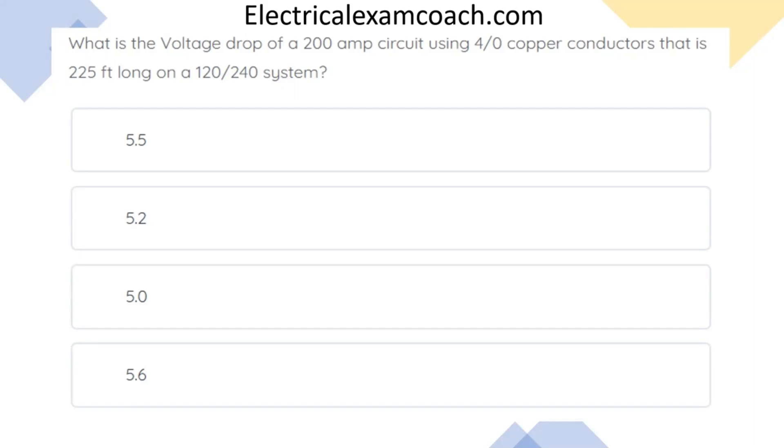What is the voltage drop of a 200-amp circuit using 4-aught copper conductors that is 225 feet long on a 120-240-volt system? And the correct answer is A, 5.5.